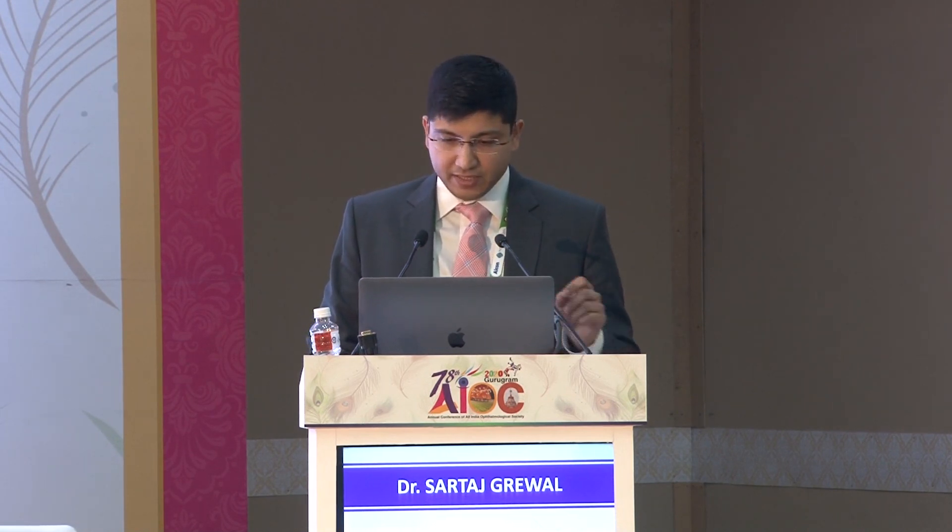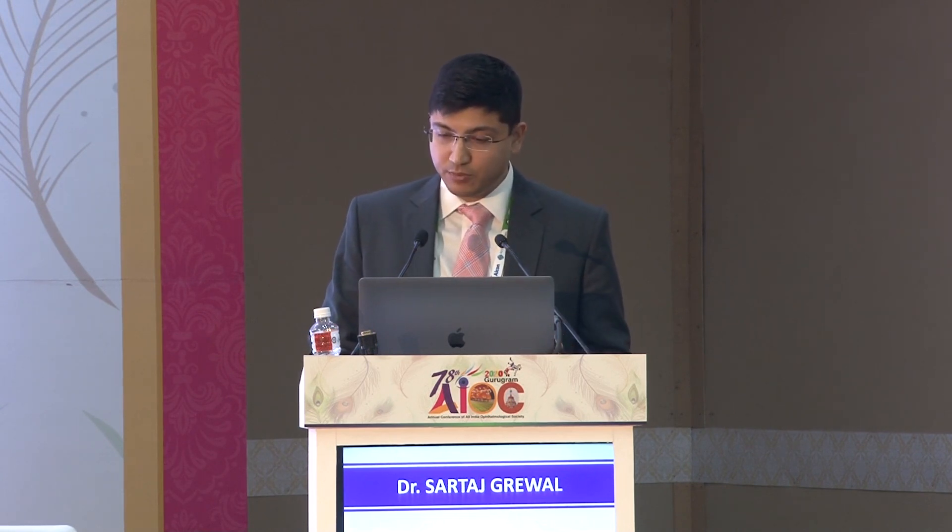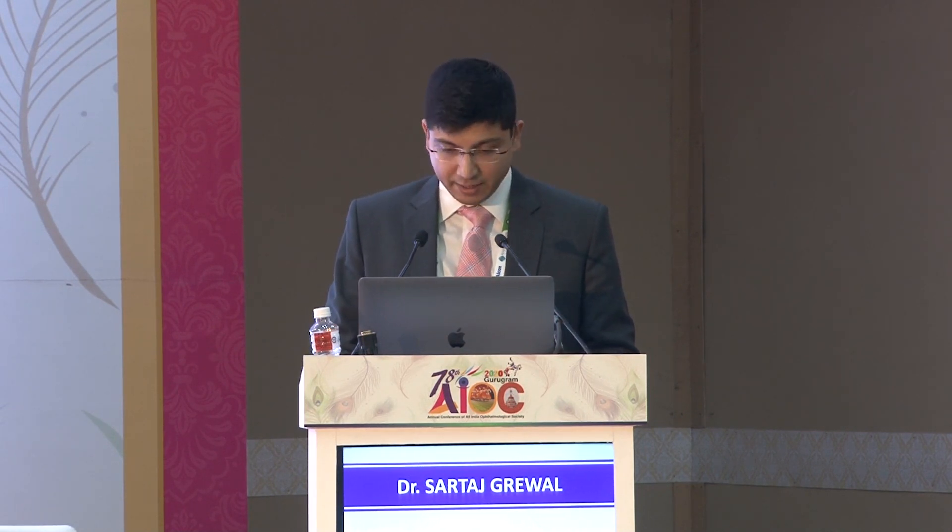Next, confirm the quality specification, which indicates the quality of data captured. It should show a white box with OK; otherwise, missing information has been extrapolated by the machine and will appear in a yellow or red box. If that is the case, it is ideal to repeat the scan to capture the data again.